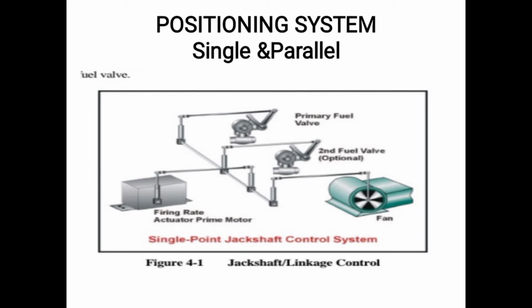And there may be two strategies: single point positioning system, and parallel positioning system. You are seeing the slide picture, which is the single point positioning system. And in the parallel positioning system, there may be two actuators. One is linked with the air flow, and the second is linked with the fuel flow. This was our positioning system.